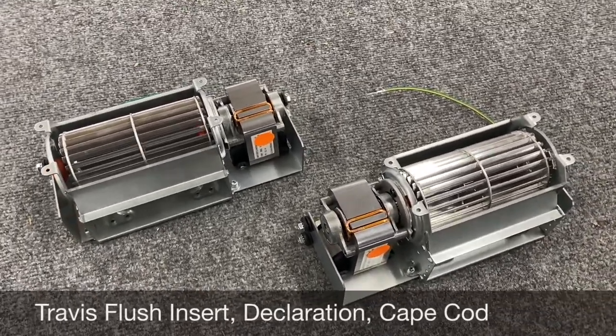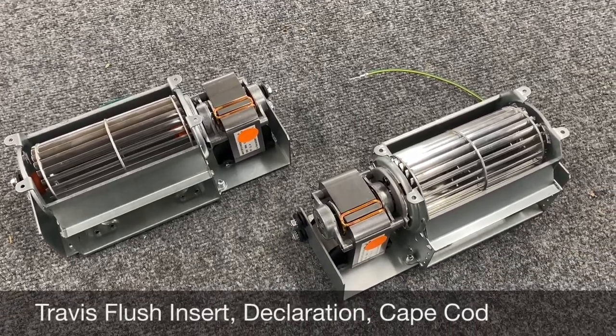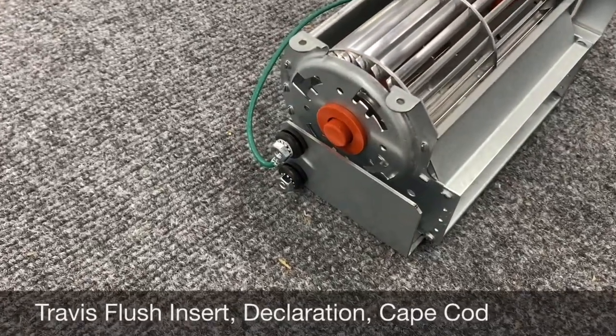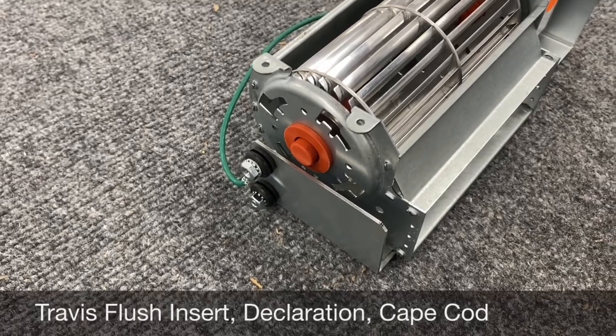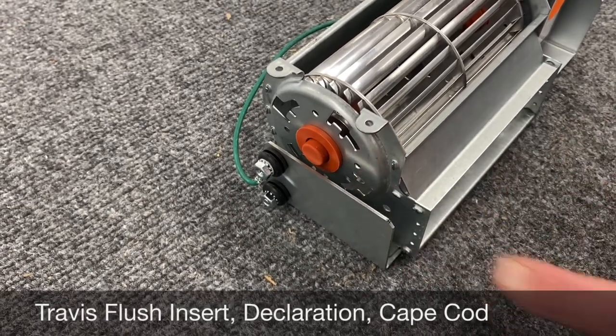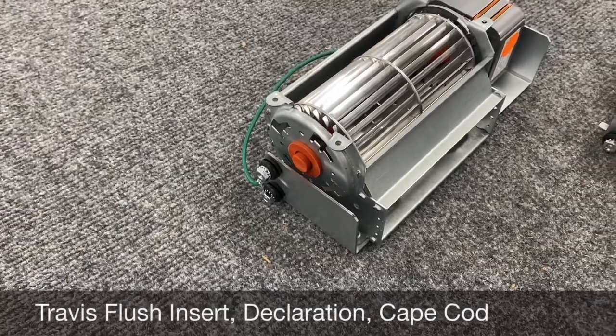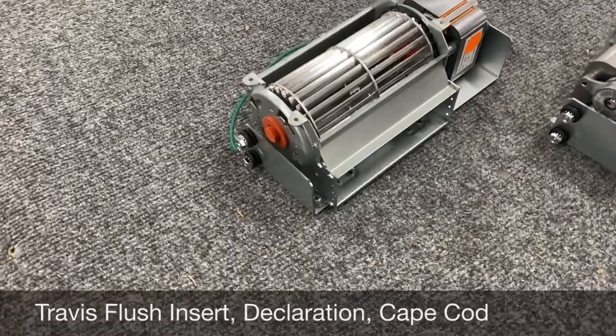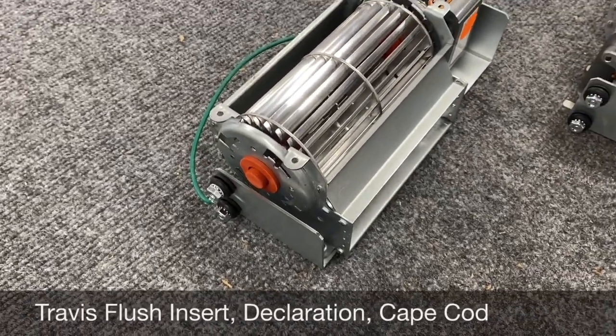The original blowers were still nice, but in a lot of cases they're using either plastic or bronze sleeve bearings on that outside spindle bearing — we call it an outside bearing, end cap, or spindle bearing. If you pop the old ones off, you'll actually see that underneath that rubber grommet is sometimes a nylon bushing or in some cases a bronze sleeve bearing. The ability for those to retain lubrication over time isn't that great.